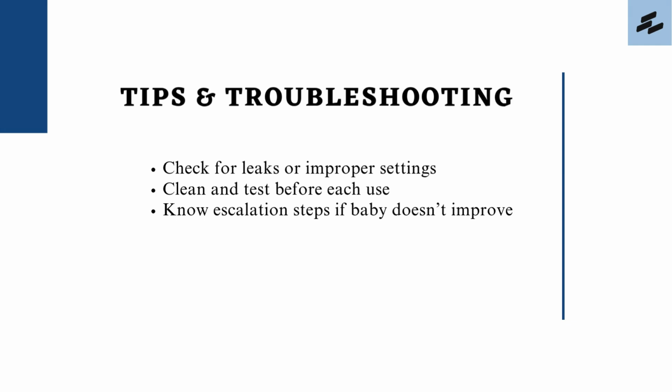Tips and troubleshooting. Before use, check for air leaks, disconnected tubing, or incorrect pressure settings. Always clean, test, and assemble the NeoPuff before placing it at the bedside. Ensure oxygen flow is working and pressure readings are accurate.